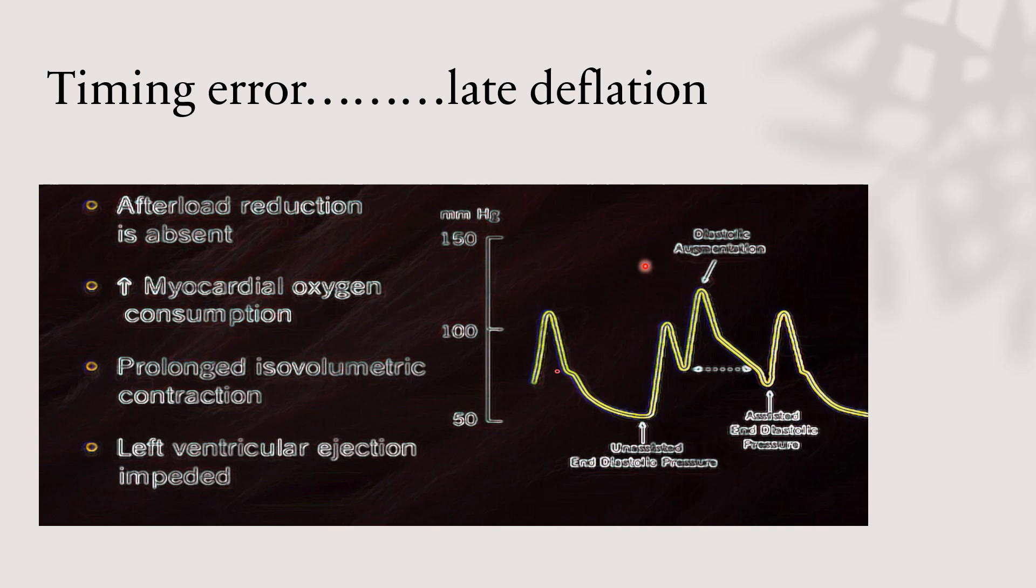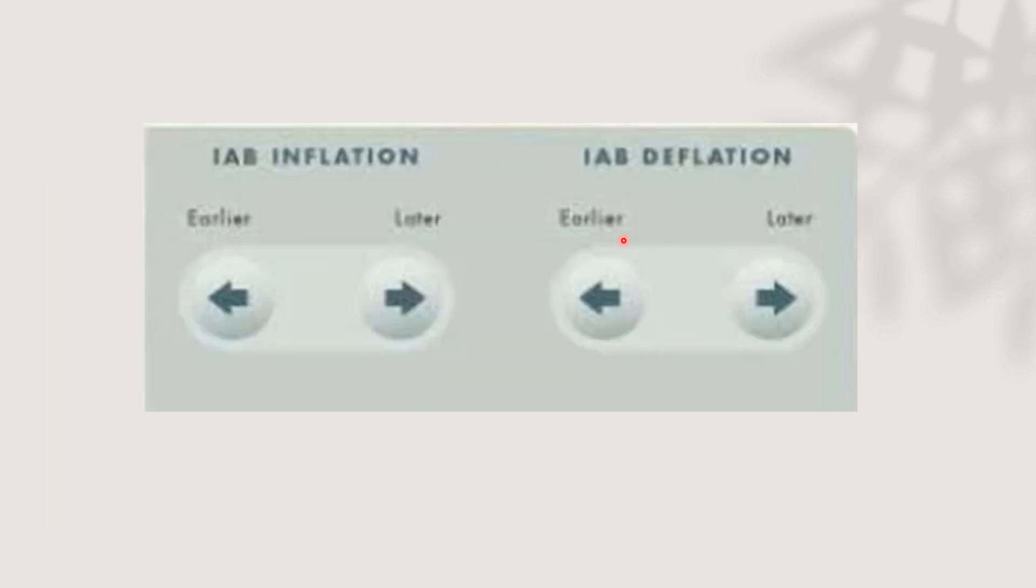If there is late deflation, afterload reduction will be absent. The balloon is still inflated, and that will increase myocardial oxygen consumption. The high pressure inside the aorta will delay the opening of the aortic valve, leading to prolongation of isovolumetric contraction, and that will affect left ventricular ejection. To solve this issue, we will press on earlier deflation till we get the proper shape of the curve.